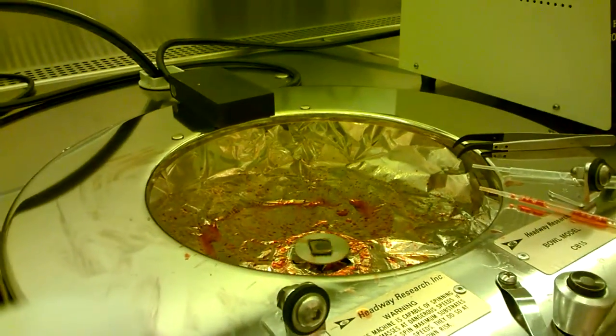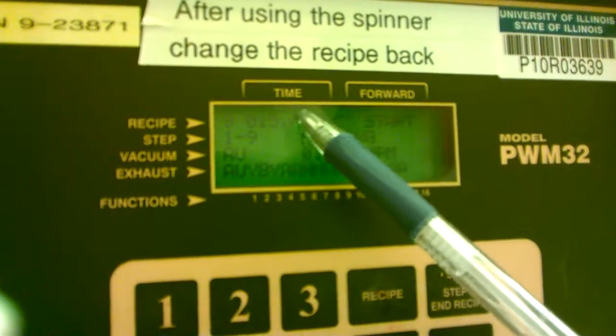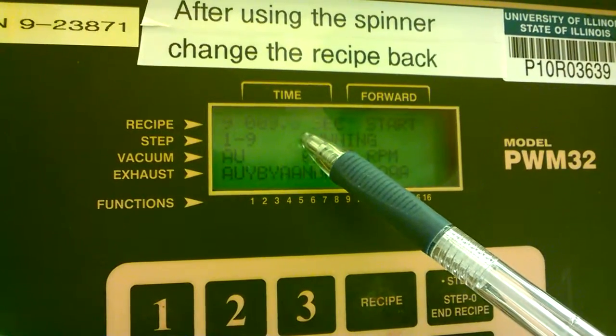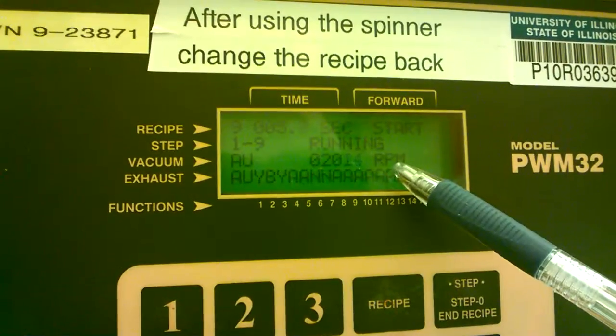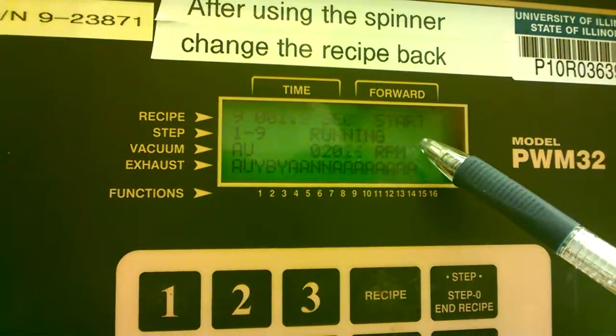So it's start to rise up. So you can check here, this is in the first step right now, and it's still rise up the rate from 0 to 2000, I remember. Right, and the time still 15 seconds. So right now we already go to the 2000 and time to go is reduced. Right, we are still in the first step. After there, here go to 0, we will jump to the second step.